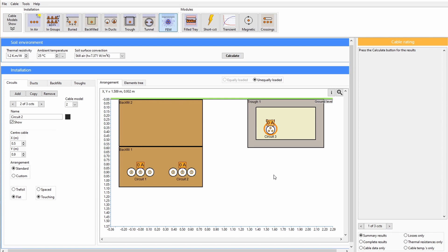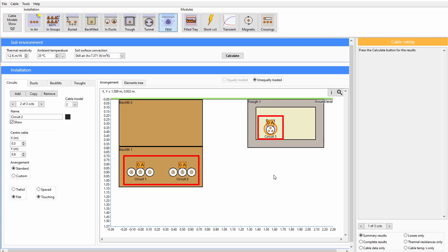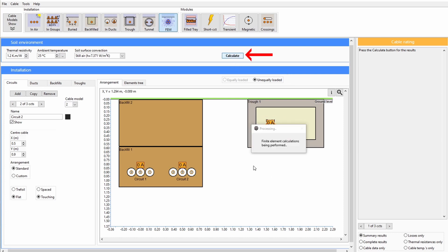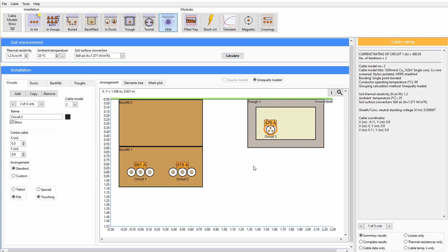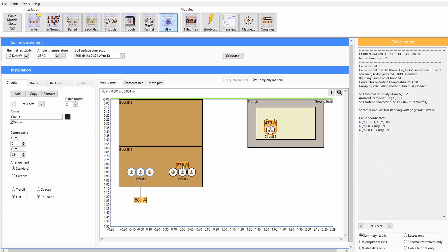For groups of cable circuits, equal current sharing or equal loading of circuits is possible. However, if there are different cable types, then the circuits must be unequally loaded. After you press Calculate, the current rating for the circuits will be calculated. Automatic meshing of the cable environment takes a few moments. Once the calculations are completed, the current ratings will be displayed. The current rating labels or names can be moved for better viewing.